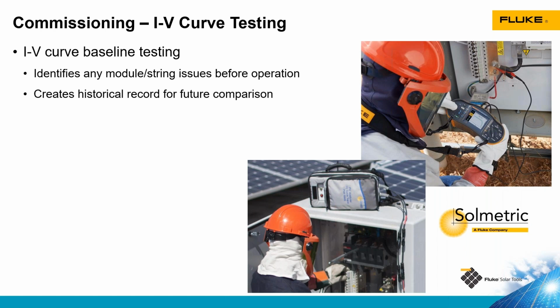Another test that's frequently done at commissioning is IV curve testing. This is a test conducted on our modules or strings of modules to see if there are any abnormalities with the production of the module. This is a test that can find problems that other tests like open circuit voltage or short circuit current testing would not be able to identify. Things like notches in the IV curve from a defective bypass diode. There's many other problems that we can see with an IV curve test.